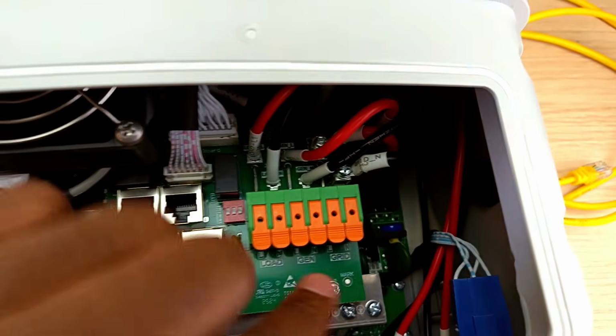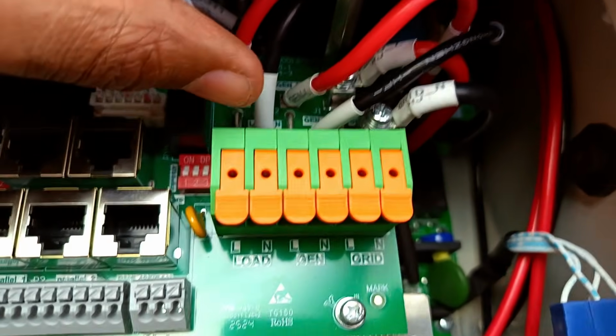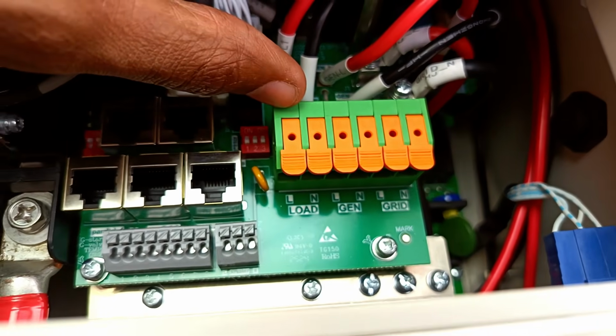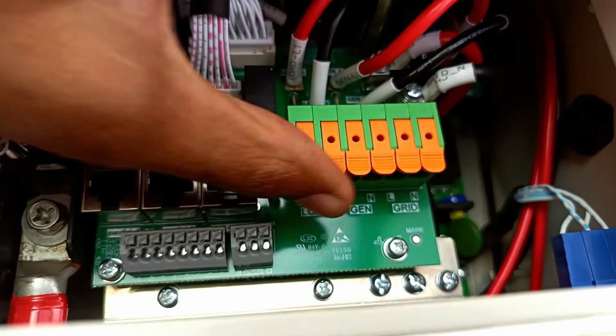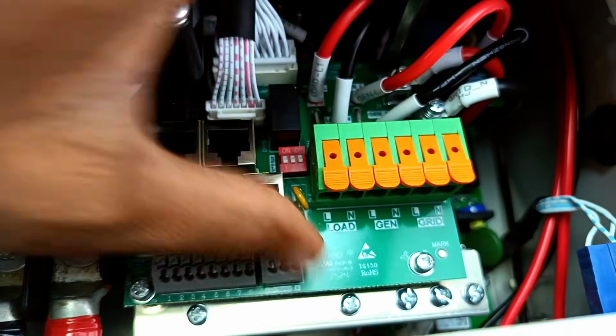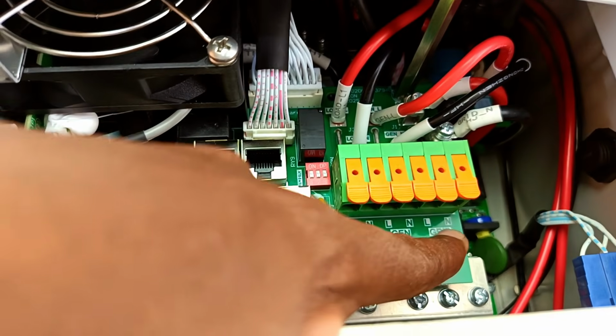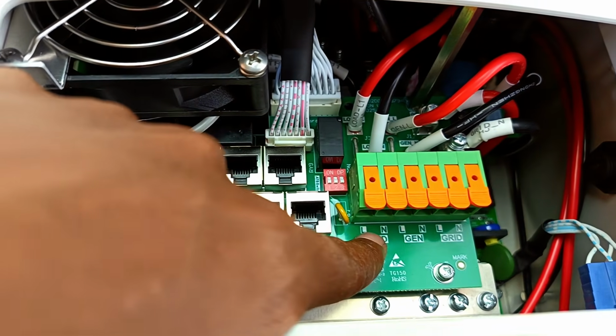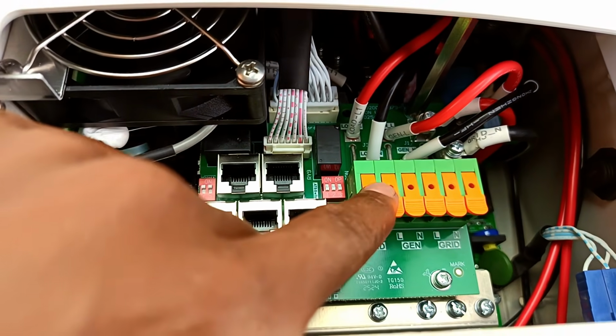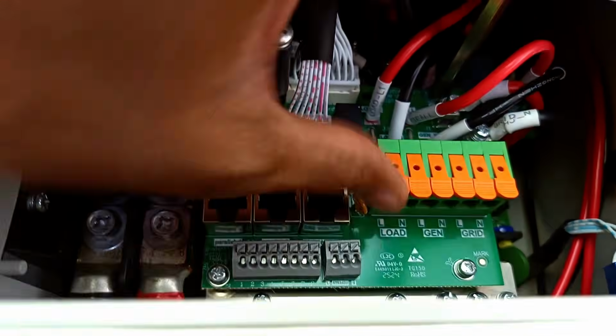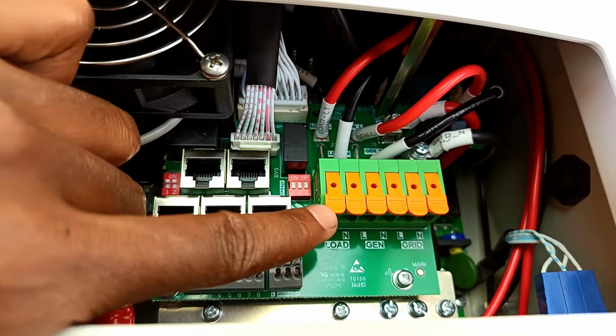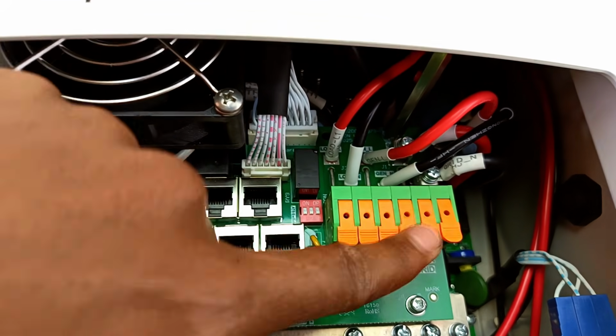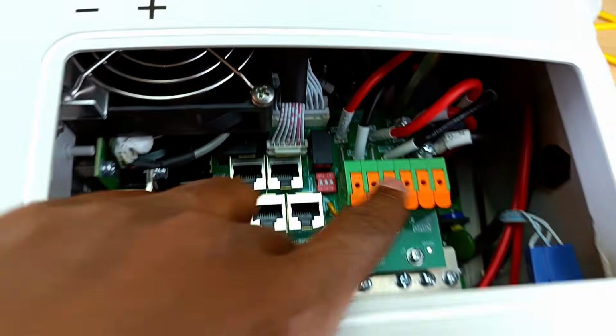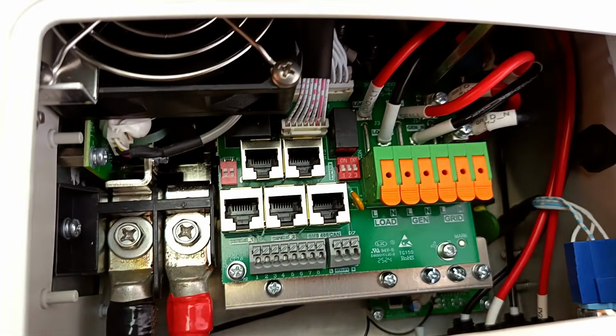Next, we have these orange connectors here where you connect your backup loads, your generator, and to the grid. The two that I'm going to use are, I will connect this inverter to the grid and also to my backup load. I do not have a generator that I will connect here. And it's very easy to connect. You just insert your cables there and you press this. They are usually very strong, even better than the ones with screws.